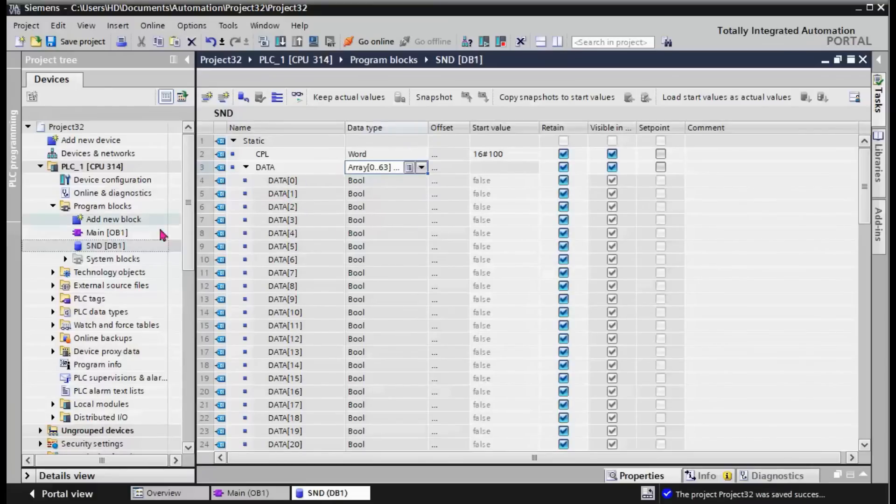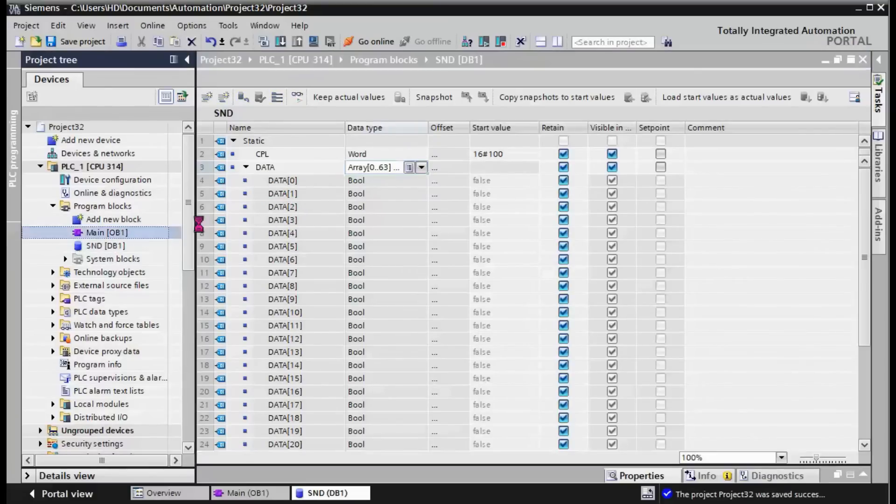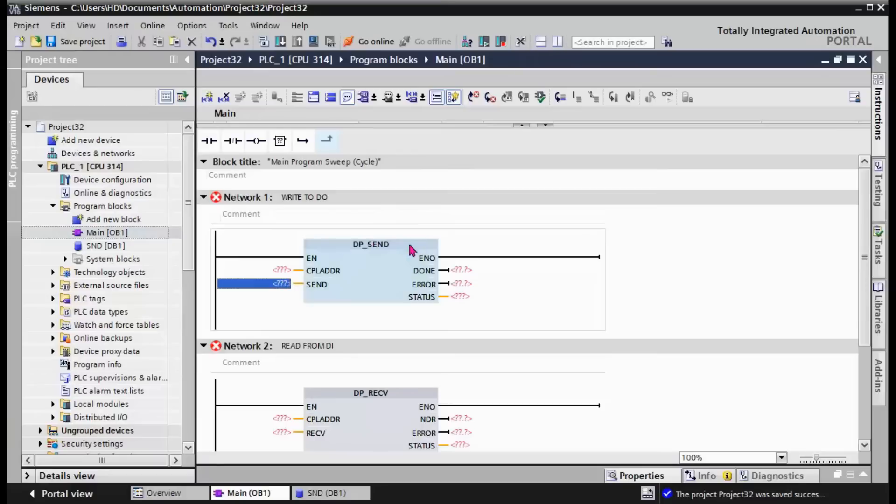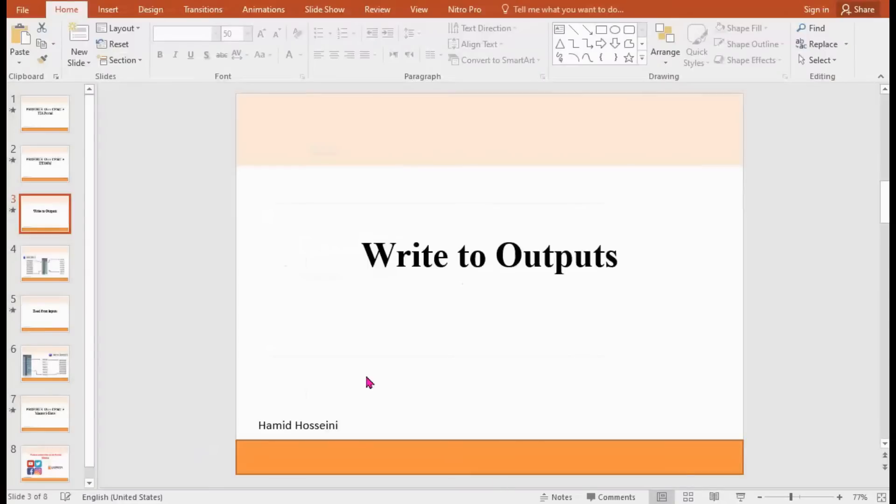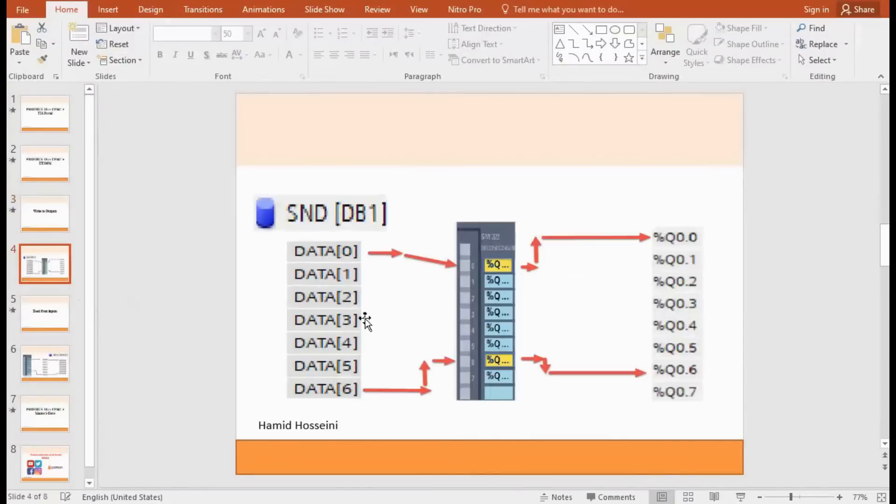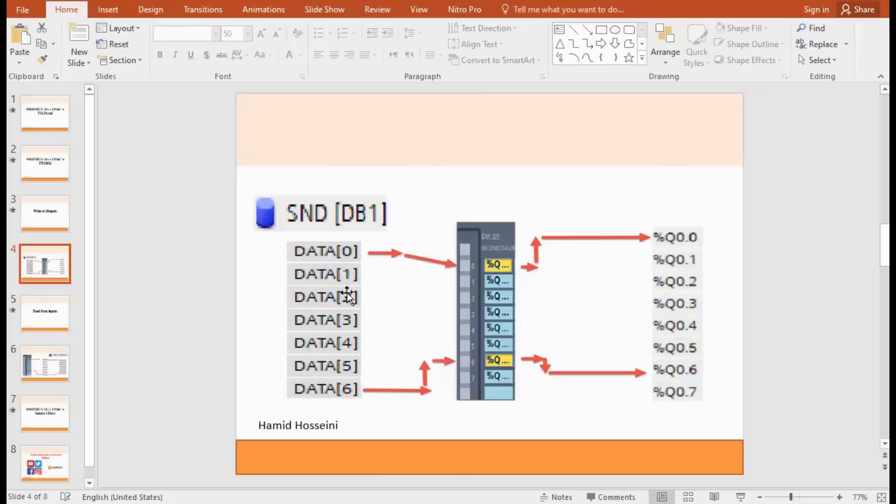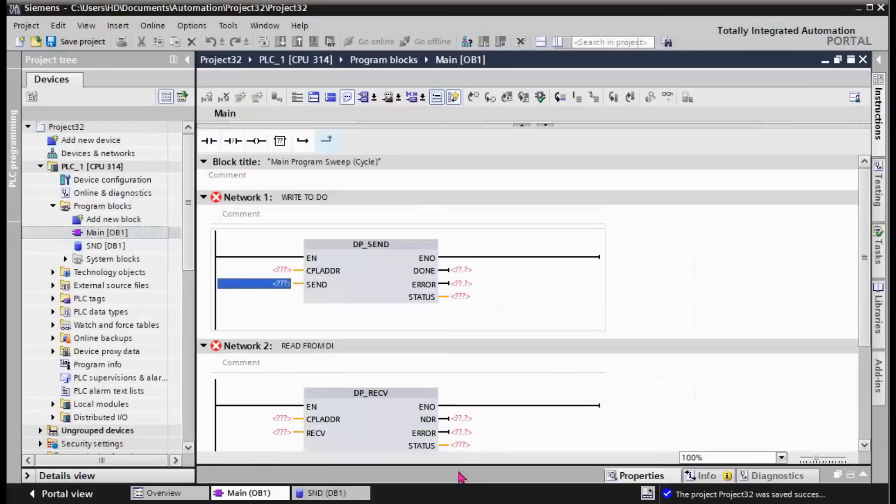We can write these values in the program, and by using the DP_SEND function, we send them on the physical module. You can see the structure here. Data in the array is sent on the actual digital output module by using the DP_SEND function.